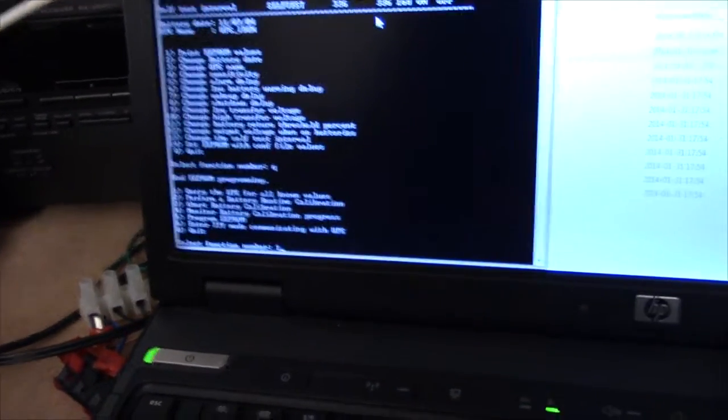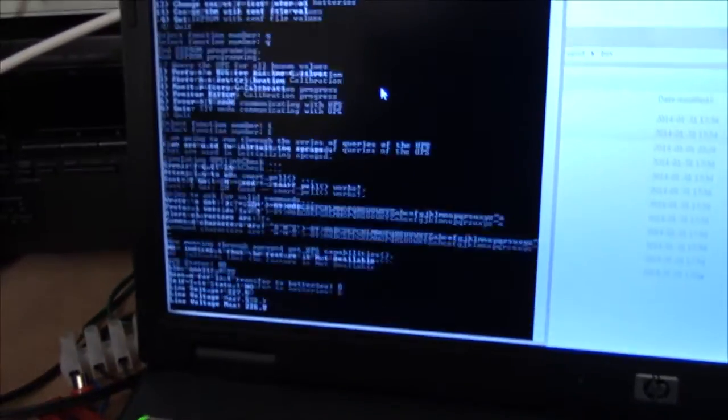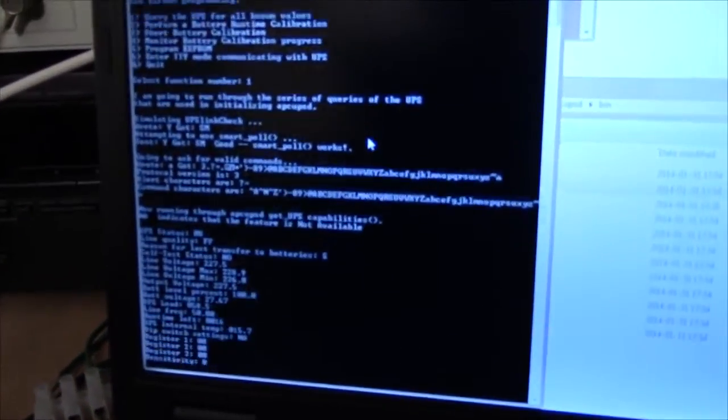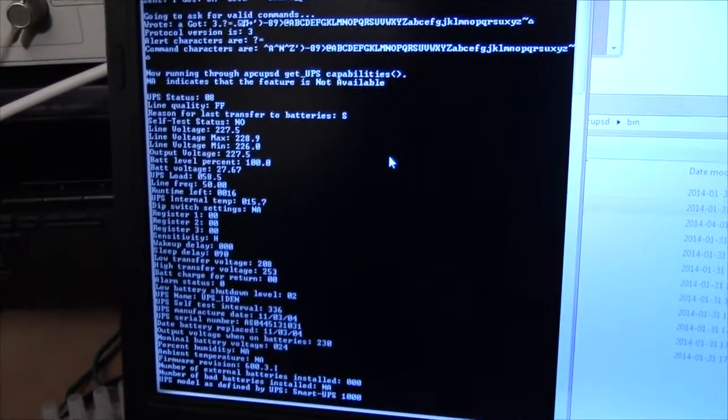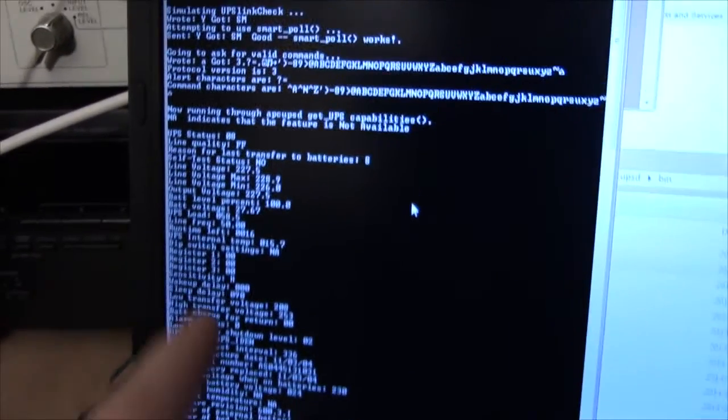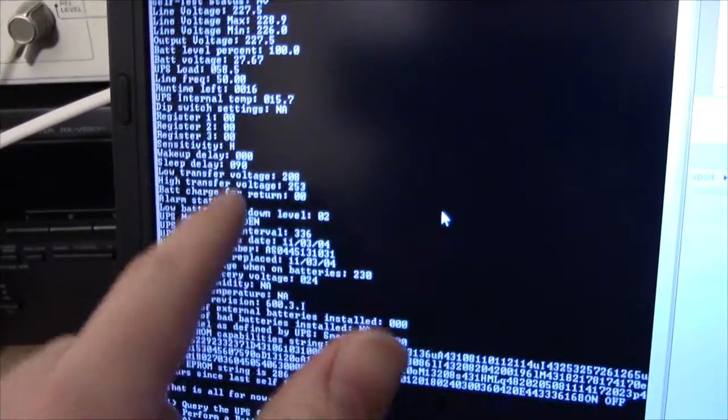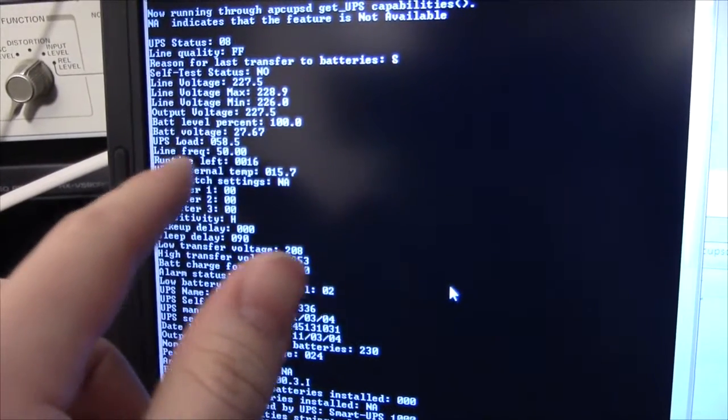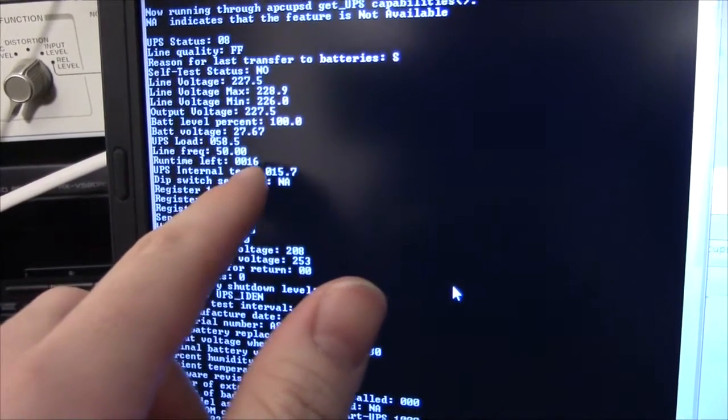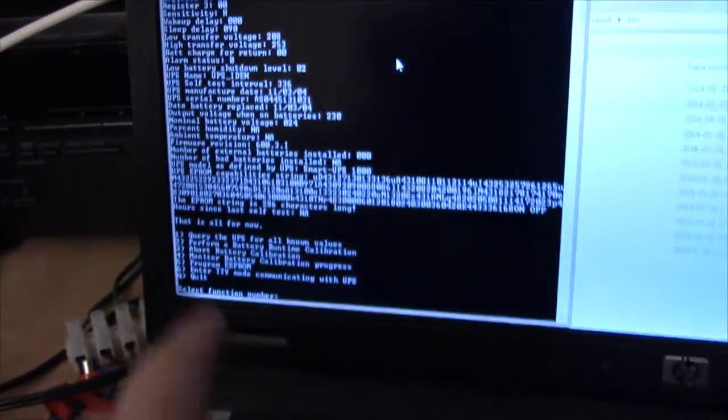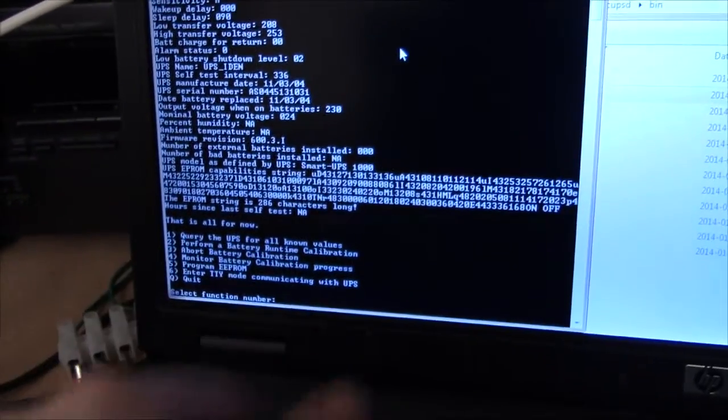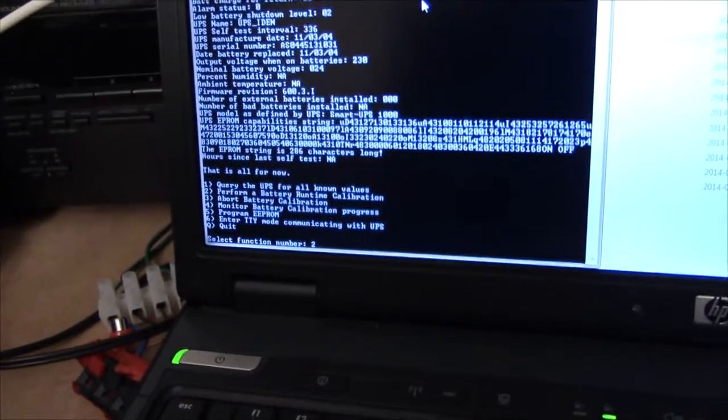We should be loading it down. Let's see, 58% load, and it thinks it's going to run for 16 minutes. So, perform a battery runtime calibration.